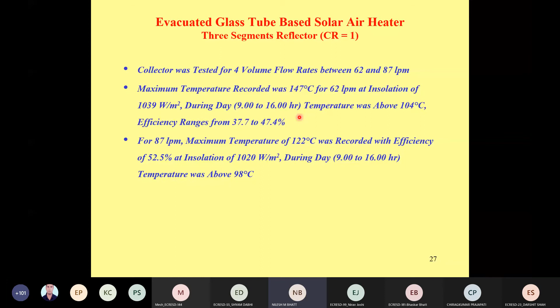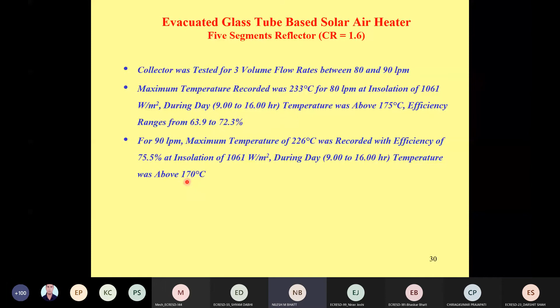The performance is very good because for this particular setup, I just want to share with you, we have used a very good reflector. We have used the sheet made by Almeco, Germany. And it was a fresh sheet, so reflectivity was pretty high. The reflectivity that we measured in the laboratory in a reflectivity test is around 94 to 96%. In the earlier case, it was around 0.8. Now it is 0.95. So that is one of the reasons for higher performance here. And one can see that with 90 LPM also you can get a temperature above 170 degrees centigrade for 7 hours of solar operation.